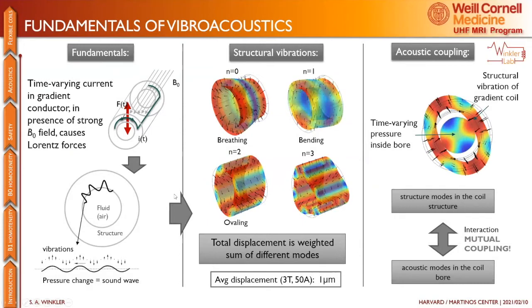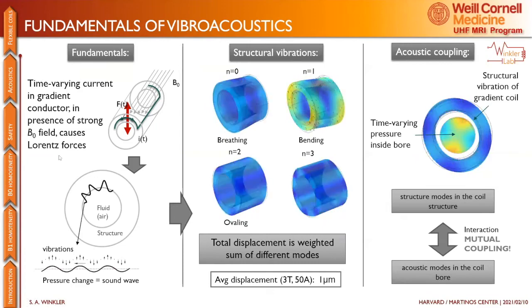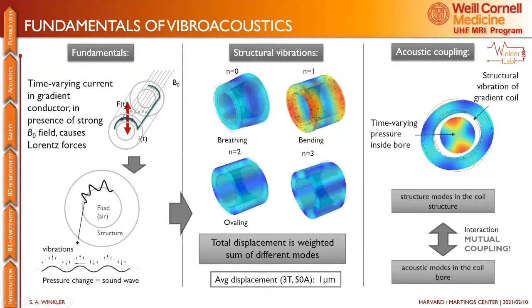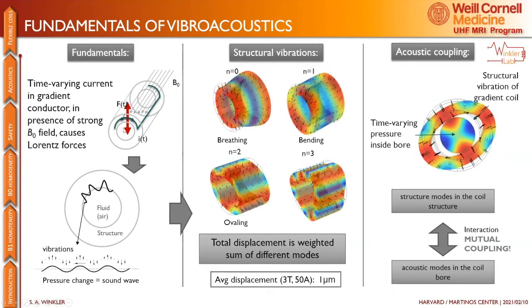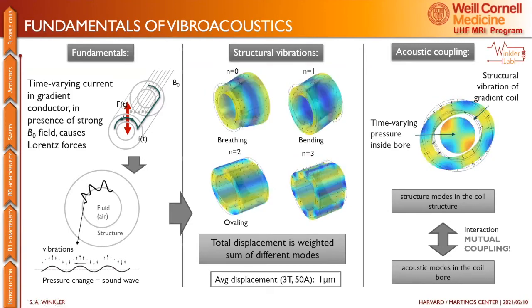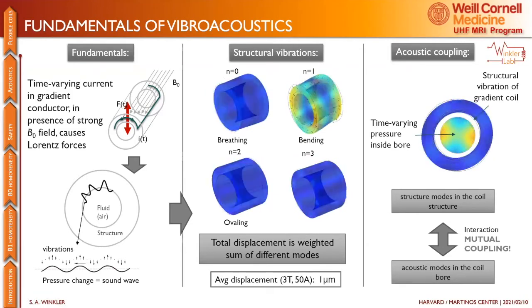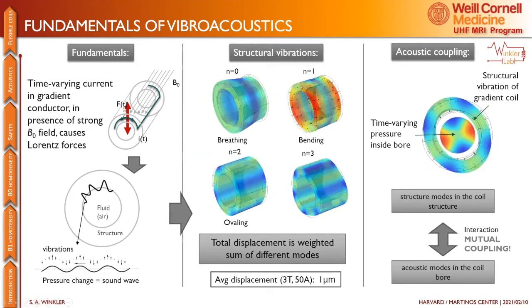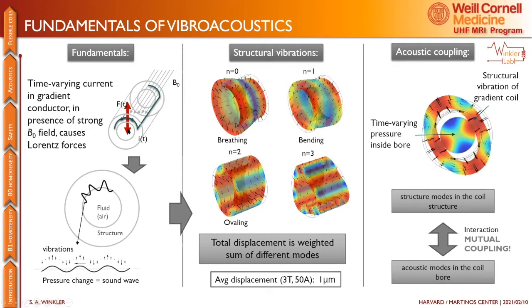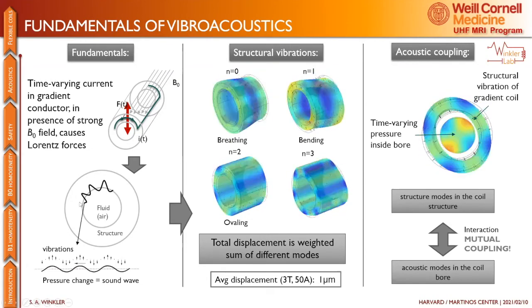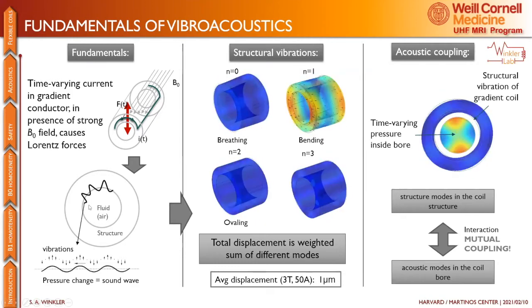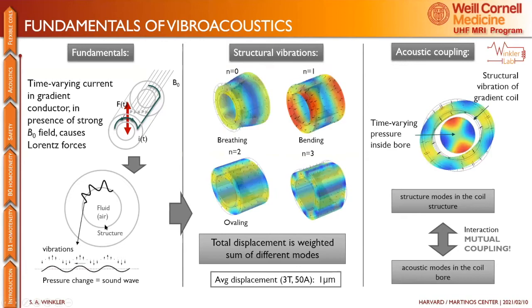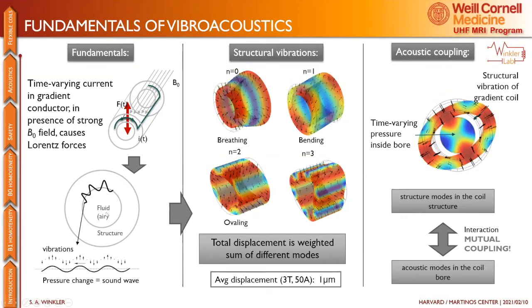You probably know most of this, but the reason an MRI scanner is so loud is that you have a very strong magnetic field, and you have currents on conductors in this magnetic field. So the Lorentz force is directly related to those two. That means you get time varying Lorentz forces, and of course that means vibrations. In turn, the bore wall of the gradient coil vibrates, and that excites a sound wave in the air cavity inside the gradient coil.